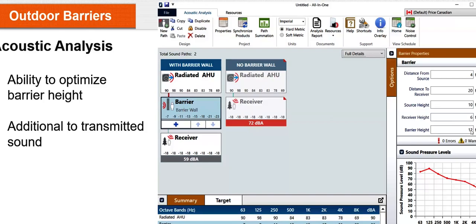Calculating now, telling you that you at least need a 12-foot barrier wall, so 2 feet taller than the unit, to get, in combination with distance, so the 20 feet in free field by inverse square law, the formula that I showed you at the beginning, you could get from 72 dBA to 59 dBA during the day. So if all of a sudden it is indeed a window in a classroom, then 60 dBA is too loud, aka you're going to need a full enclosure on that unit.